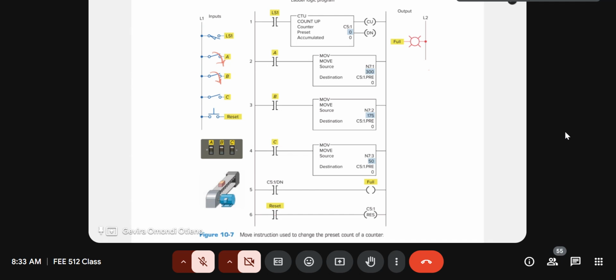So if I pressed switch A and then immediately pressed switch B, then the PLC will energize or activate the second move and ignore the first move. Okay? So the last instruction given, because remember these are input instructions, the last input instruction is the one that is executed. So in this case, even if I pressed all the switches, it is the order in which I pressed them. The last one that was pressed is the one that is going to be executed.